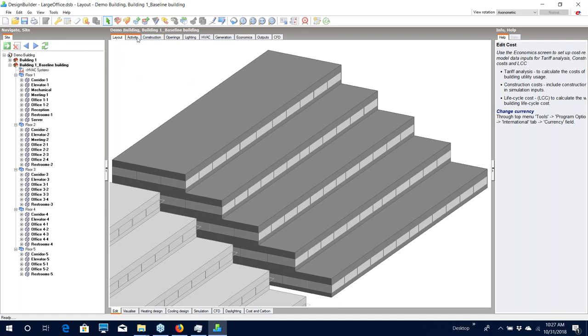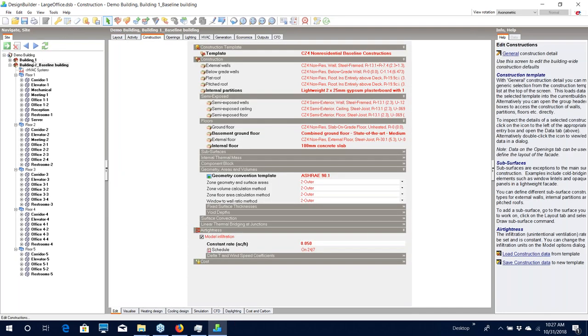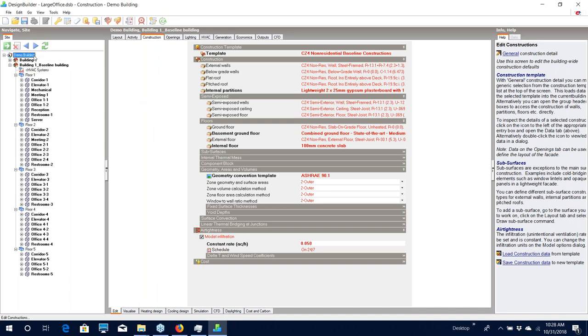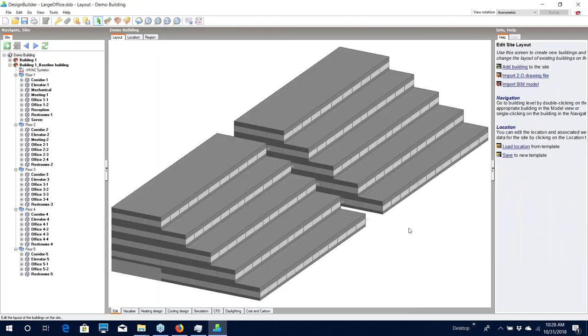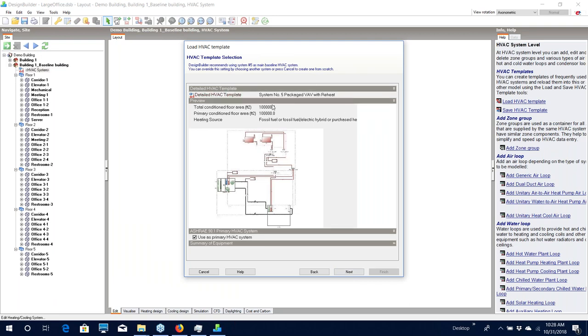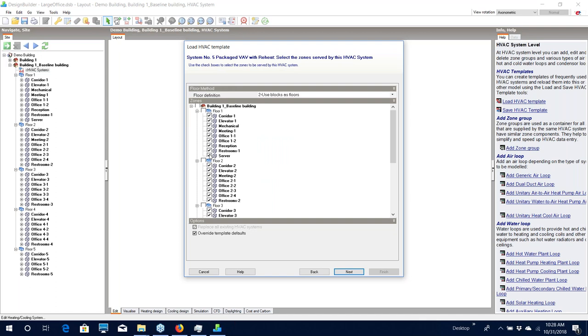Now we have the baseline building created next to our proposed, and you can see clearly that there is an overhang on the proposed building and no overhang on the baseline building. Looking at the Construction tab, we can see that it's been changed from what we had selected in our proposed building to the correct constructions for our climate zone. With our baseline building created, we have the geometry, internal gains, and schedules, but we need to generate our HVAC system. Being a much bigger building at 100,000 square feet, this time we're going to use a packaged VAV with reheat as the primary HVAC system.